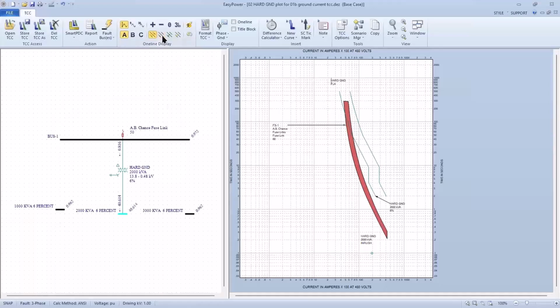If we check a single-phase line to ground fault, now our fuse protection needs to take into account this offset, which is the solid line. If I'm relying on my fuse on the primary side, I need to make sure I'm clearing that primary fault. Again, we're looking at the 480 volt range, and we're assuming that we want protection per phase to be more sensitive than a single line to ground on the secondary of the delta-Y transformer.